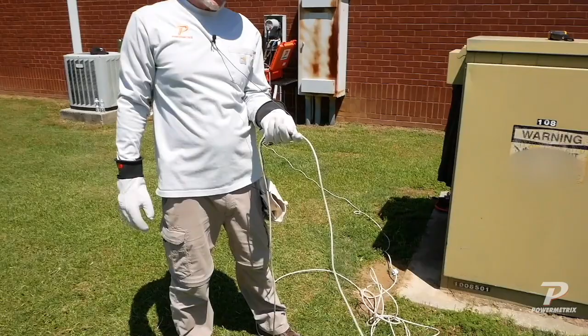Troubleshooting 101, right? So what Jonathan's doing is making sure he doesn't have either a bad flex or a bad probe adapter cable. That's why he's moving the flex connection to see if the problem follows the flex. If I take the B phase flex and swap it with the A phase flex and still get the 14% or whatever, then I know that's not it. But if I swap and put the B phase flex on there and it tests just fine, now I'm looking at that flex - the A phase flex might have a problem. So I'd put the A phase flex over on B and test it, and if it came out again, I'd think I've got a problem with my flex. Or you can move your connections on your probe adapter cable and follow that to see if it's maybe in the probe adapter cable, okay?